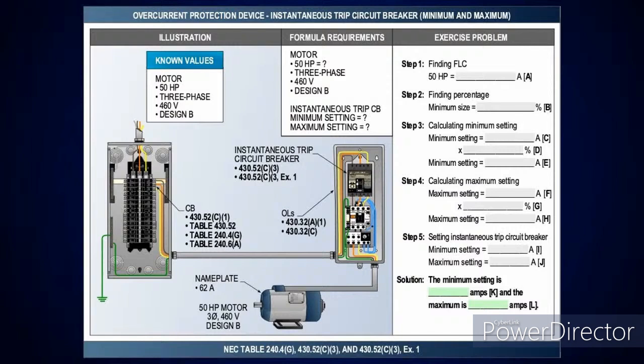Well, in the 2023 code, this is interesting. I would ask: how do you think the manufacturers determine the minimum and maximum size for that overcurrent device? When they design their equipment, it's designed taking into consideration what the code is. I can go through many examples showing where the National Electrical Code is used, and how the manufacturer has to take that into consideration, plus their own UL standards or any other standards that affect that piece of equipment, to get that listing and labeling. Now, they put minimum on their nameplate. I'm not saying every AC unit has minimum and maximum, but there are ones that do.